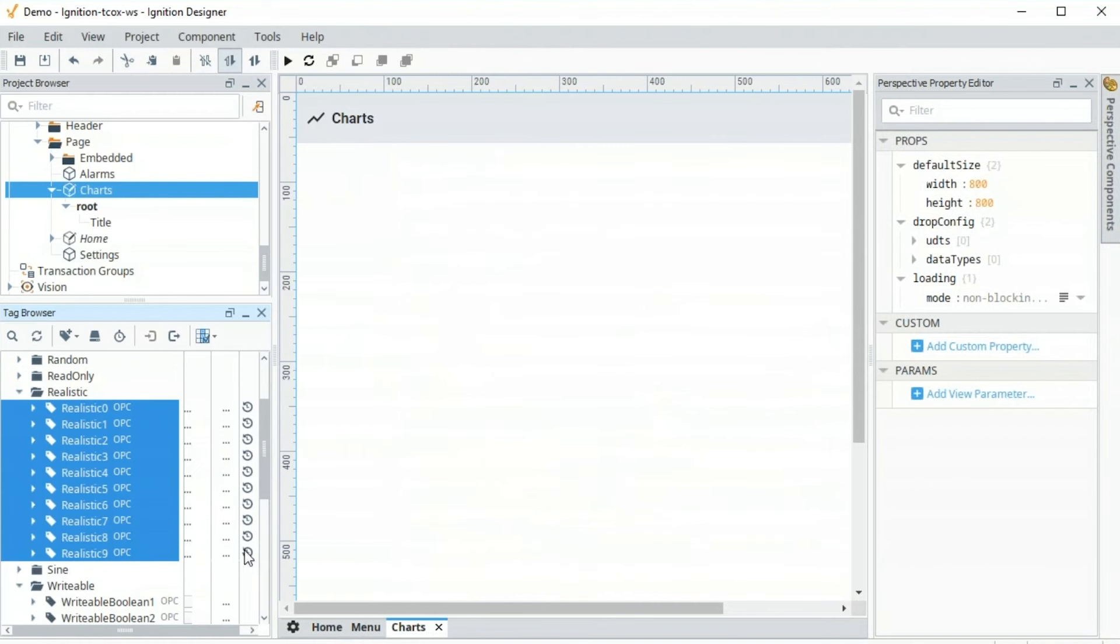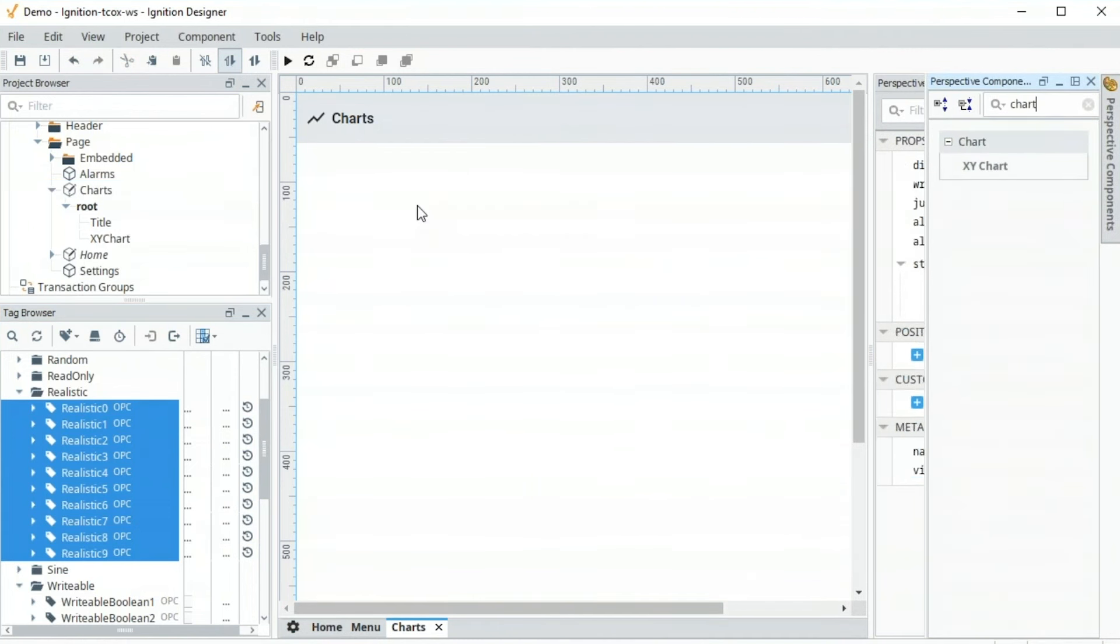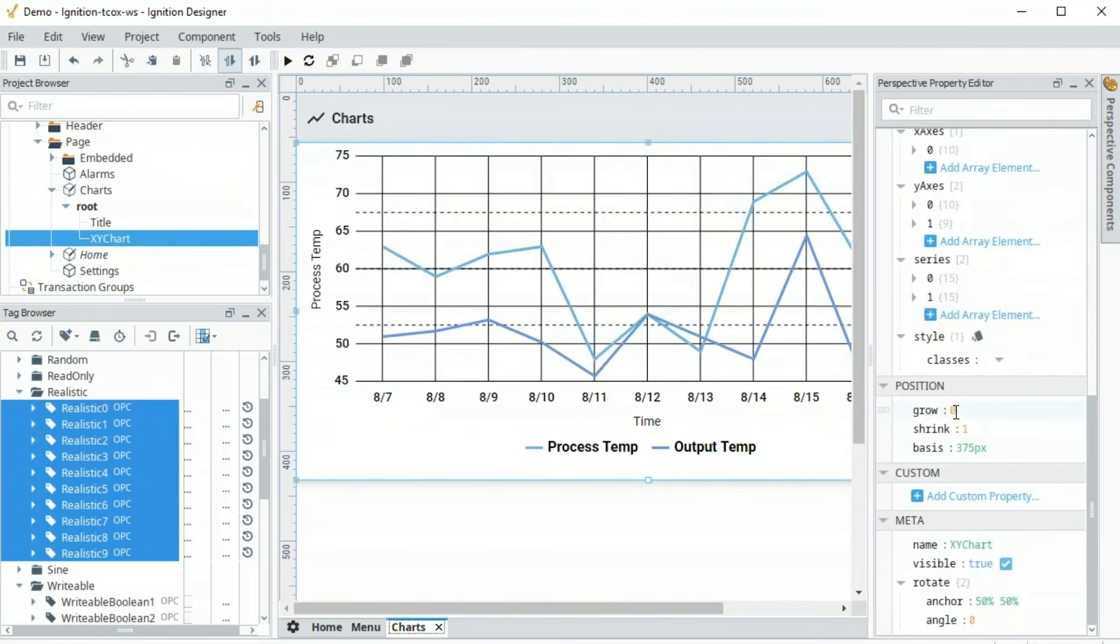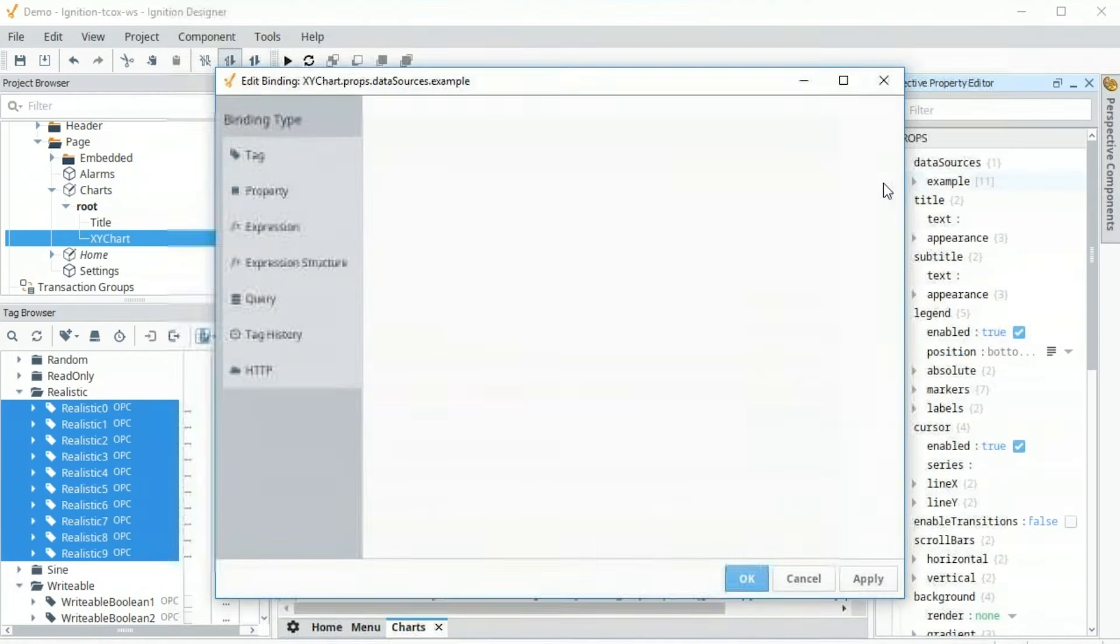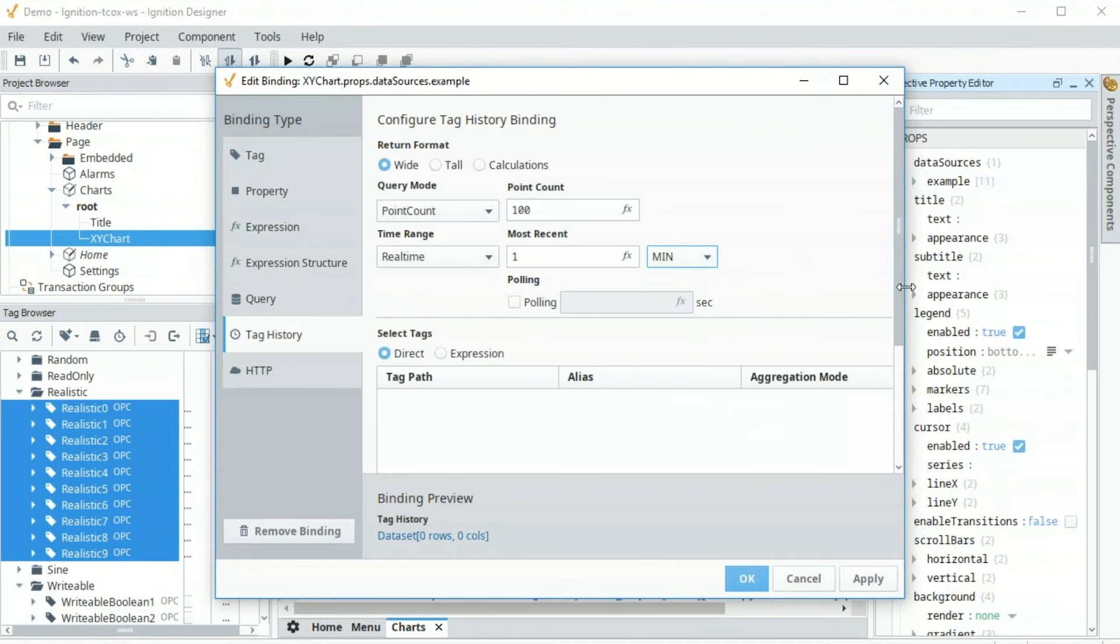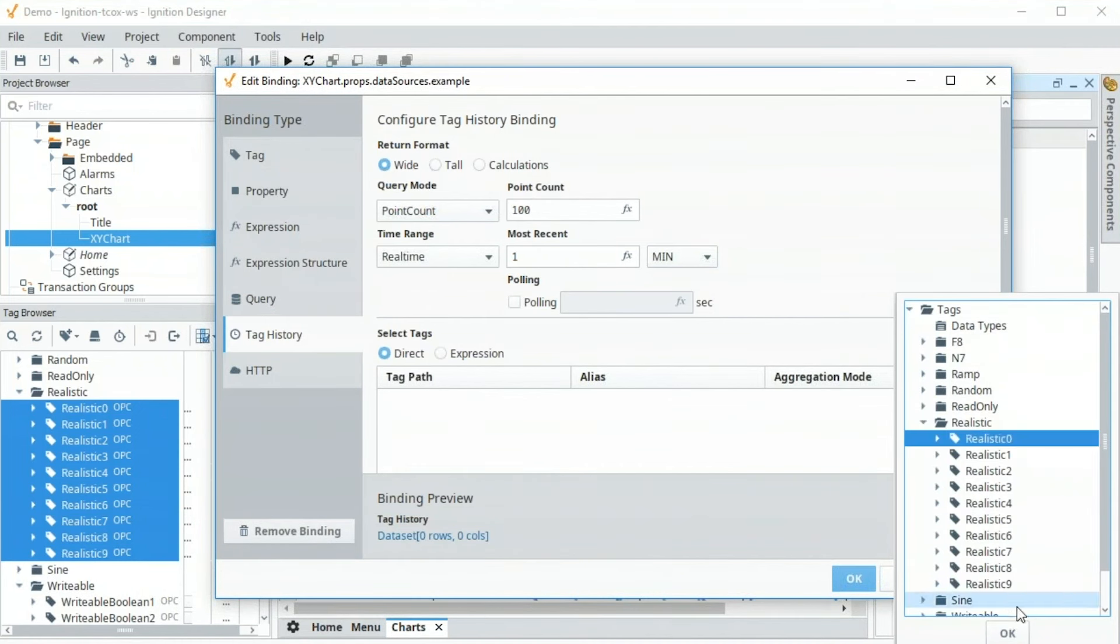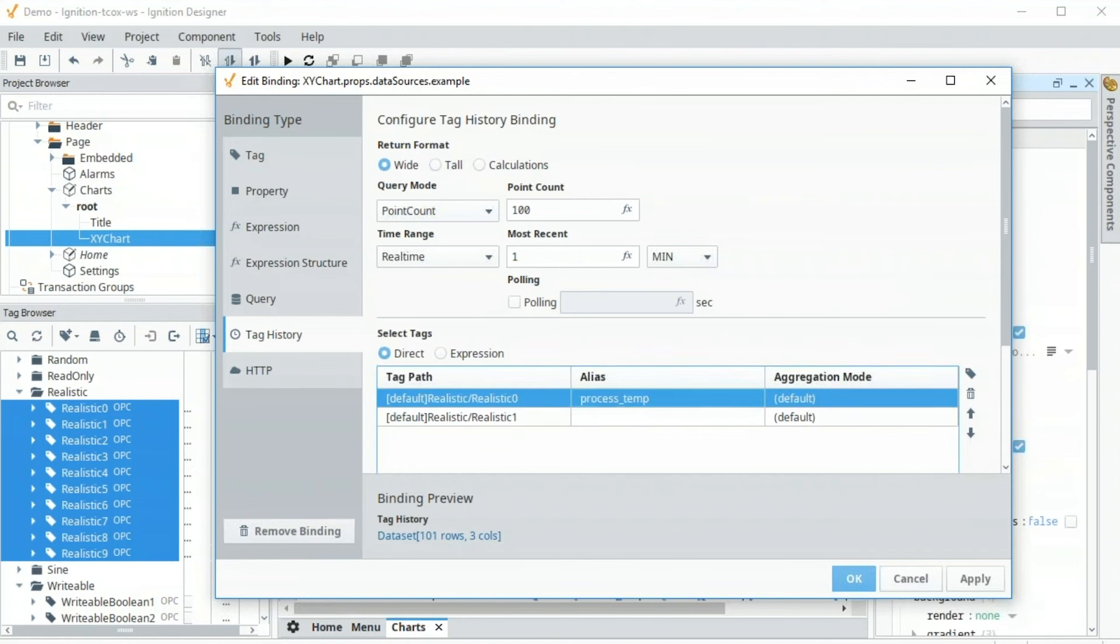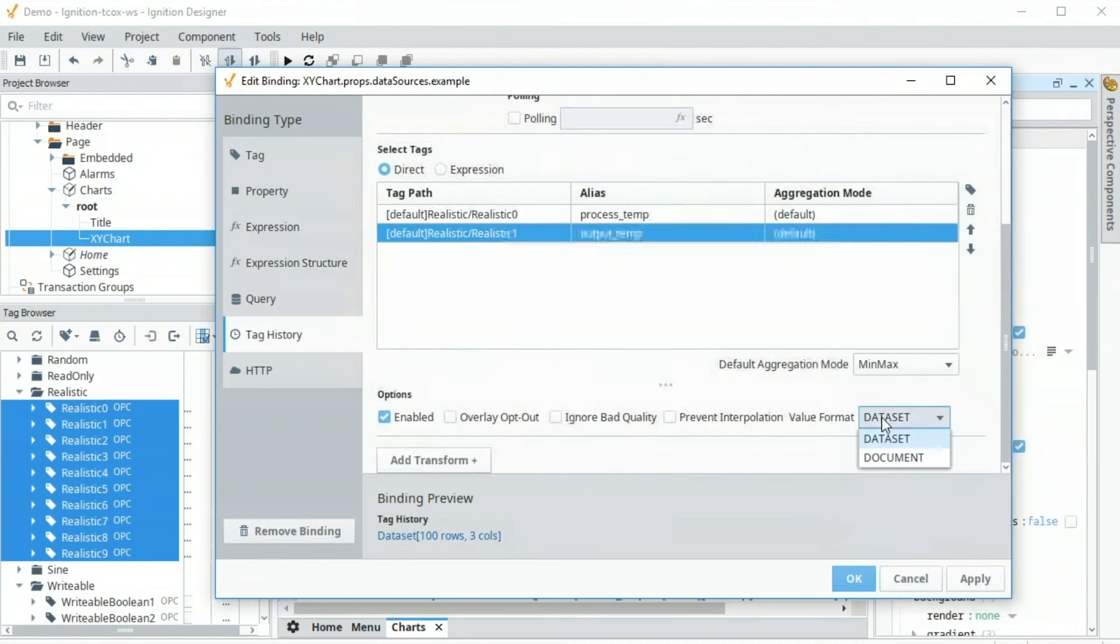This little icon here lets us know that those tags are being logged. Now we can bring on to this screen the XY chart. So I'm going to just put chart and find that component, drag it over here. We're going to make that grow, be the full size of the screen. And what I want to do is bind the data set, the data source, to tag history. And I've only been logging for just for a little bit here. So I'm going to just select the last one minute of data. And I'm going to select the tags I want. So let's go down here to our realistic zero, and let's go to our realistic one. I want to give them better names. You could have called those tags something better, but instead I'm going to give them an alias here for a process temp and output temp. And then I want to see what that data looks like, so I'm going to bring it back as a document.